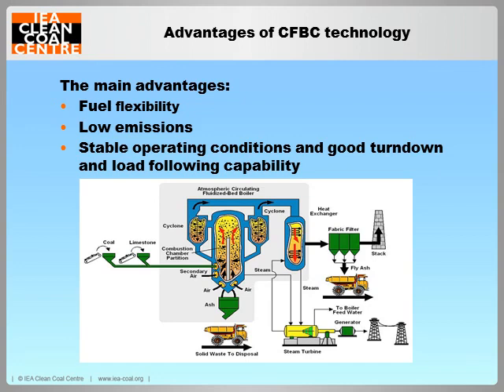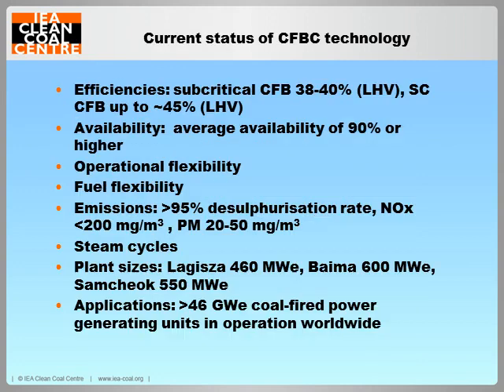CFBC boilers have low emissions of SO2 and NOx, without addition of expensive flue gas emission control systems, due to the in-furnace desulfurization and the relatively low combustion temperature. CFBC systems have good combustion efficiency and provide operational flexibility. The current status of the technology is such.